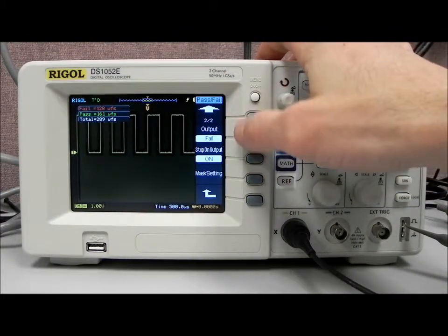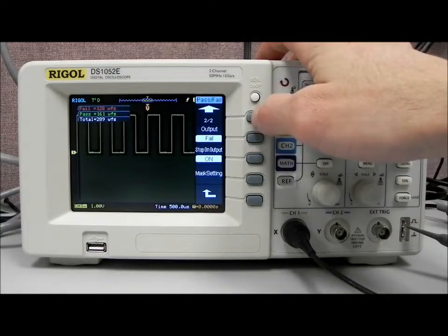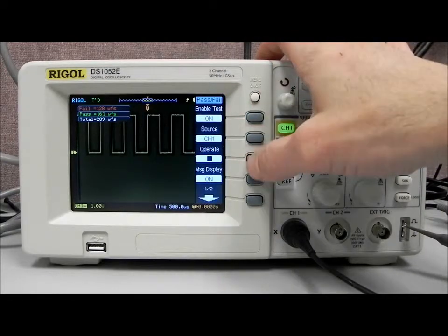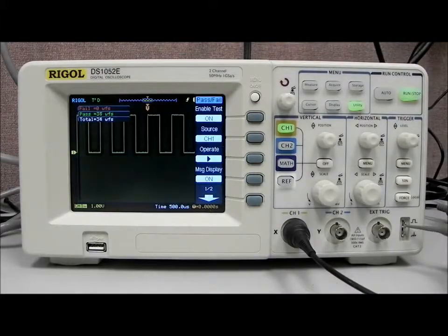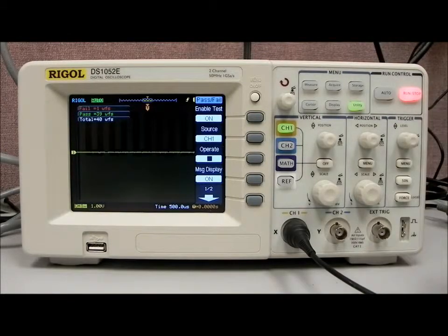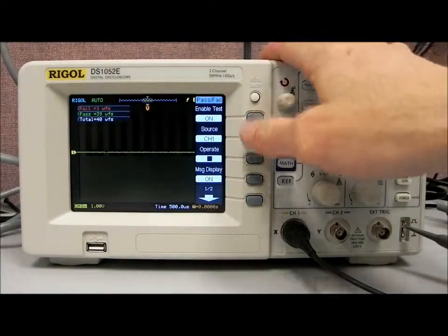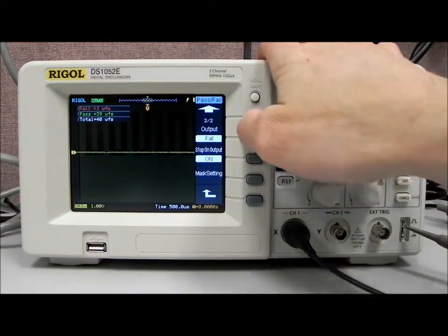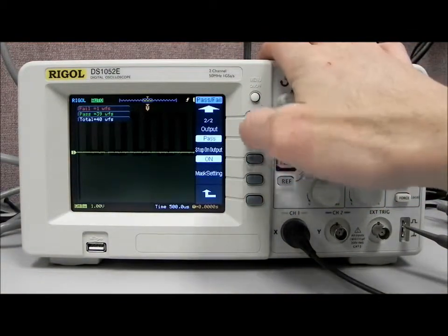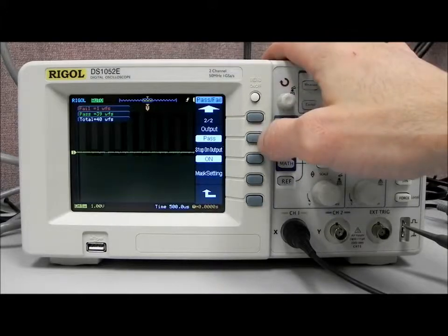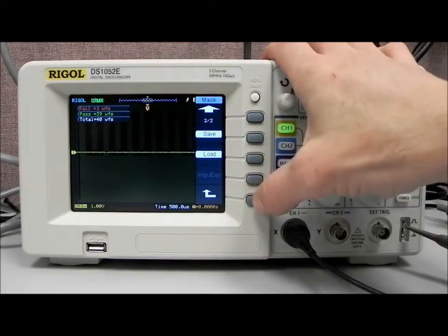output, and we're going to have the output on fail. So that means that when it fails, the box is going to stop, and you'll see it will quit taking waveforms. So we've gone into stop mode, and now we've only had one fail, but that fail has stopped the instrument from taking any more data. It's also through the output on the back of the instrument, it's also disabled or sent a failed signal. We've configured it to do that by using the output fail, and then we can also do an output on pass if we'd like. So very flexible.